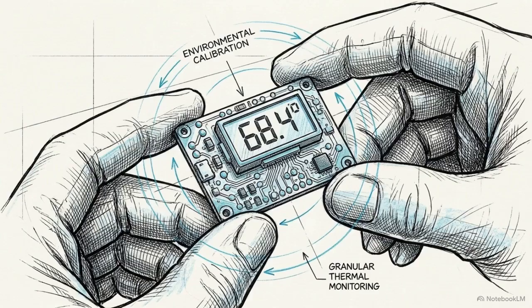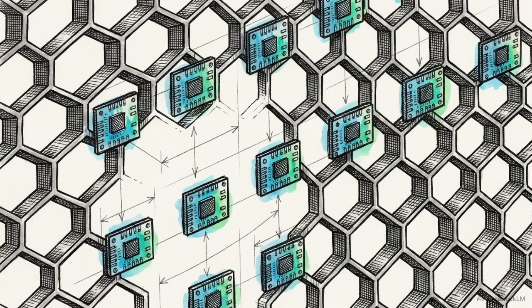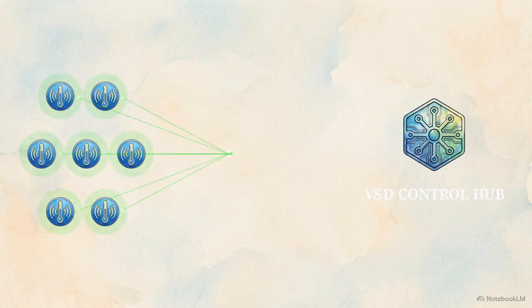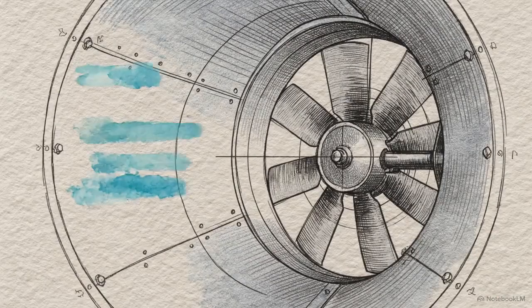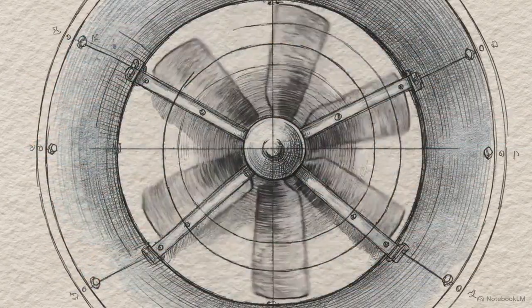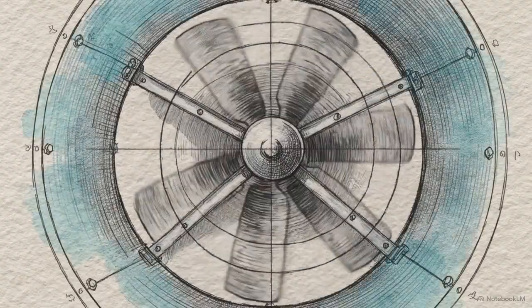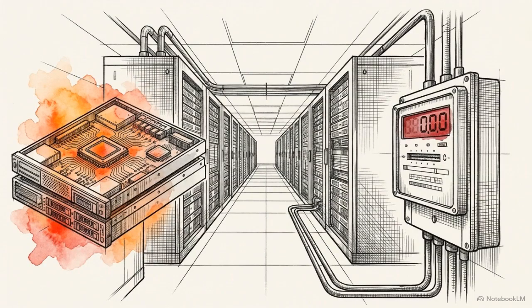For precise internal control, facilities install thousands of highly sensitive environmental sensors directly onto the individual server racks to monitor temperatures down to the square inch. This granular data feeds directly into variable speed drives, or VSDs. Instead of blowing air at a constant blast, VSDs dynamically spin the fans faster or slower, matching the exact real-time demand of the servers. Modern thermal management is a constantly recalibrating equation, continuously balancing massive computational heat loads against the steep financial costs of electricity.